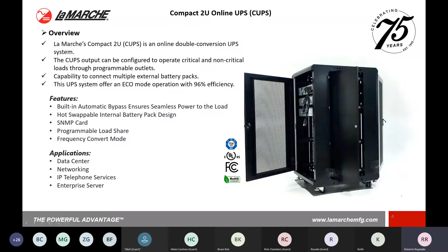They are all 2U modules that you see here. The 2 kVA is the same output but runs on a 48 volt DC bus versus a 24 volt on the 1K, and the 3K on a 72 volt DC bus. So what that would simply mean for you is that the battery packs here, if you can see the picture on the bottom end, would have to be replaced using a different set of configurations as far as 24, 48, or 72 volts. And again, your external battery packs would have to be ordered to match your DC bus input.